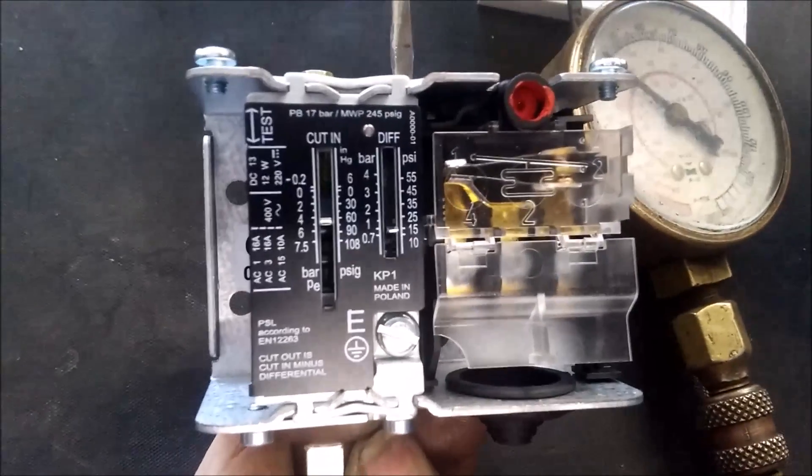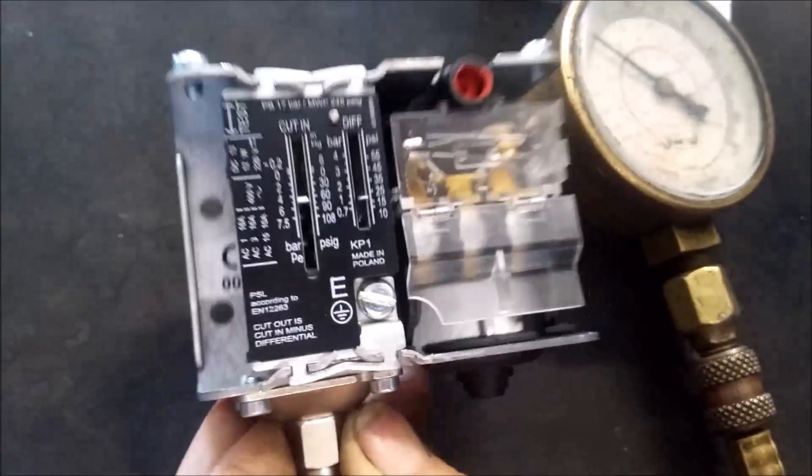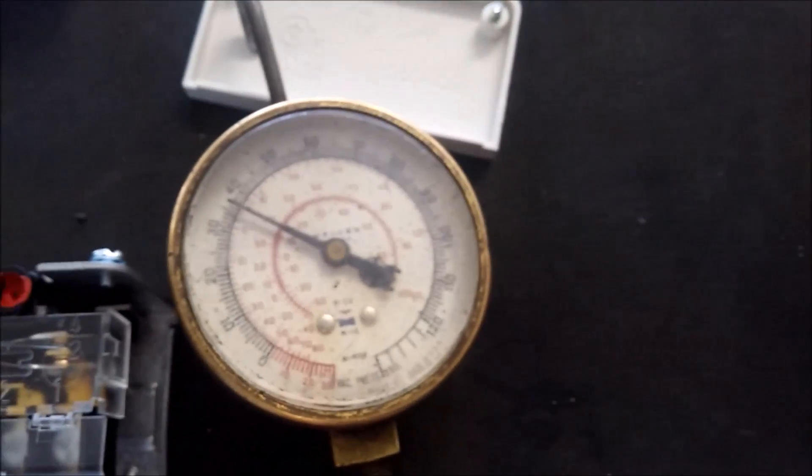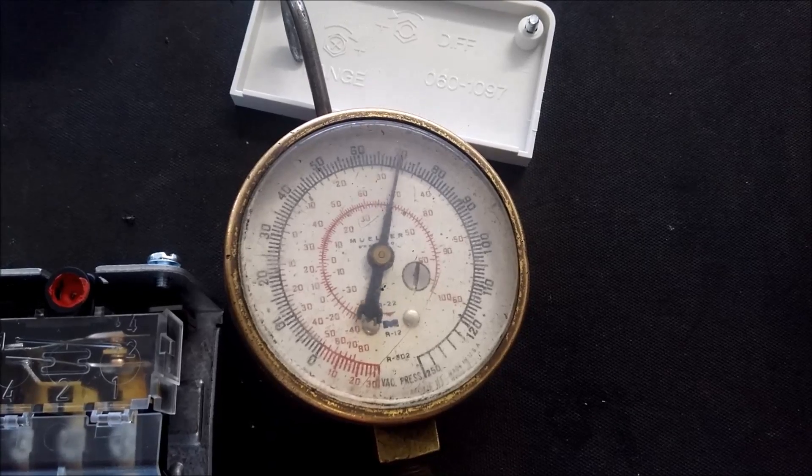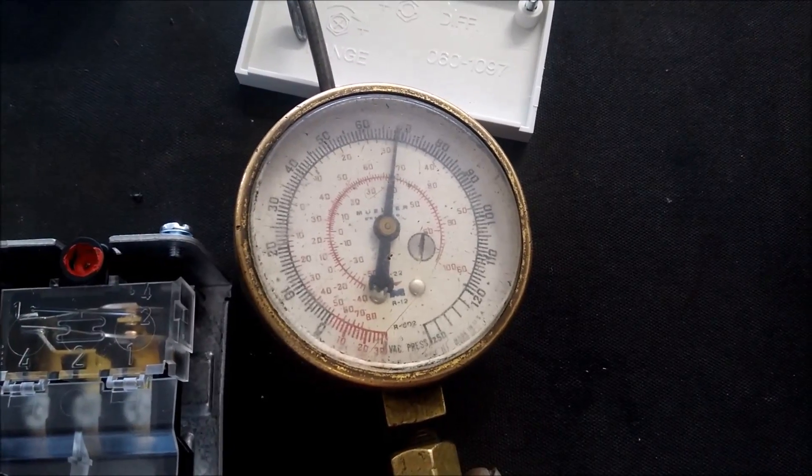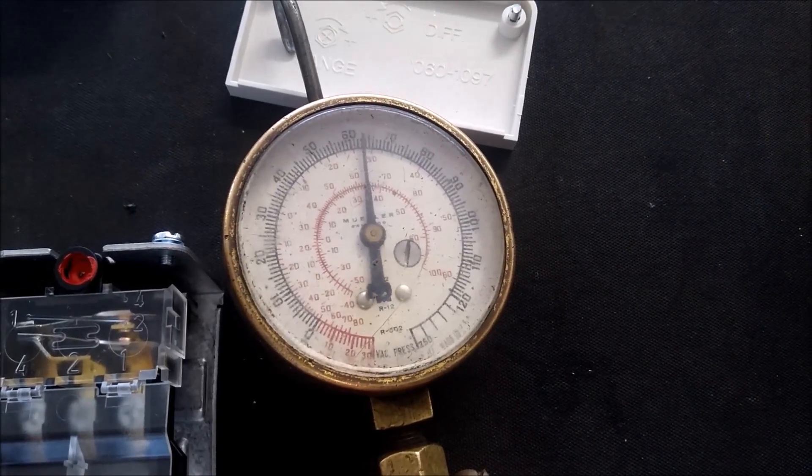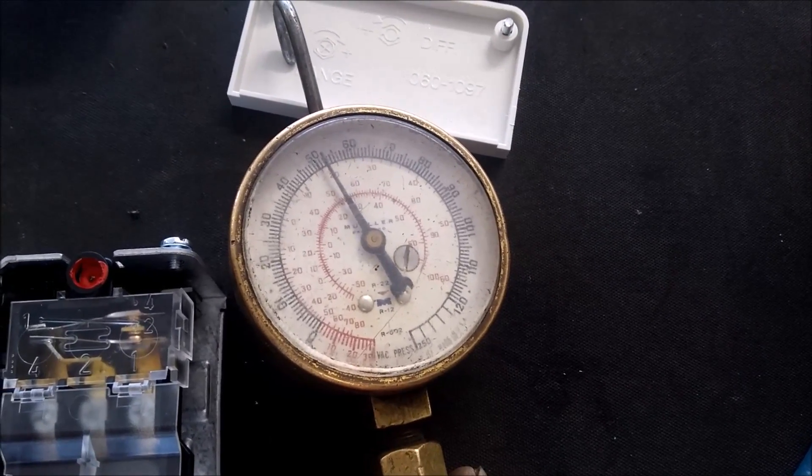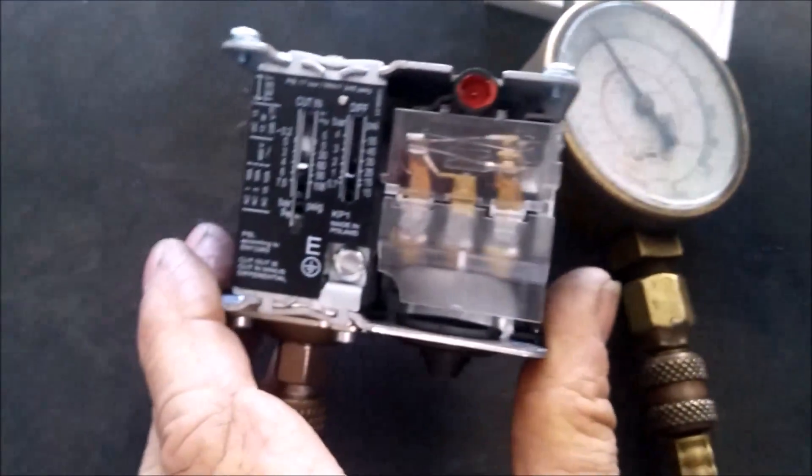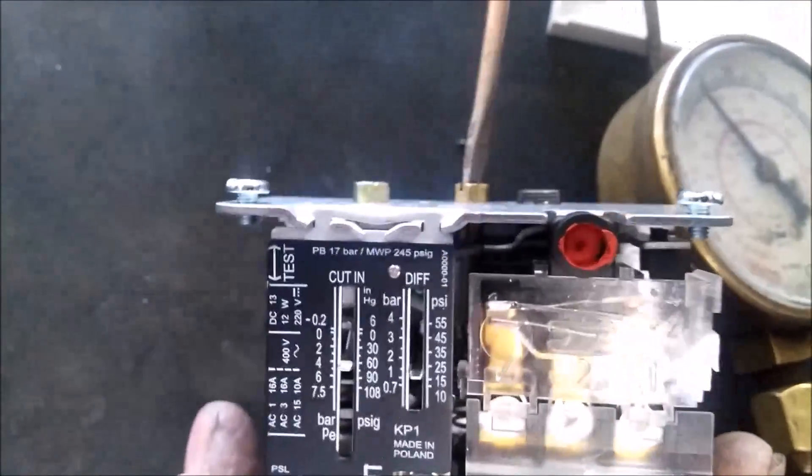And I'll just blindly turn on it a bit. And then we check what we've done. If we've gone the wrong way, the 70 stays the same but it will be closer. If we've gone the right way, that pressure will drop quite a bit before it switches on. So it did drop a bit, so we can adjust a little bit more on it.